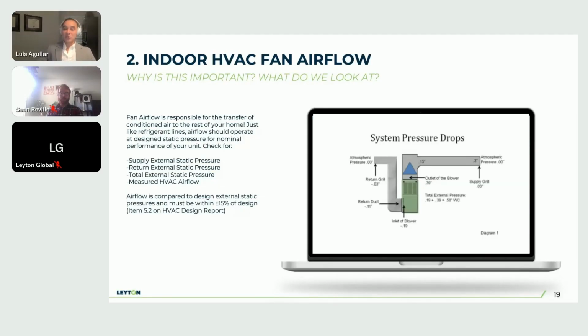All right, so just like there's a pressure requirement or a pressure change requirement in your refrigerant, there's a certain static pressure, or we call external static pressure, for your AC unit. So if it's operating as intended, the manufacturer will provide external static pressure difference between the return and the supply. And so if that external static pressure is being met, then the airflow within the unit is operating how it's intended to. And so what does that mean?